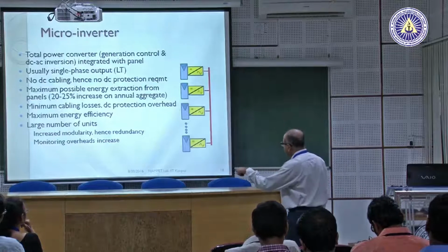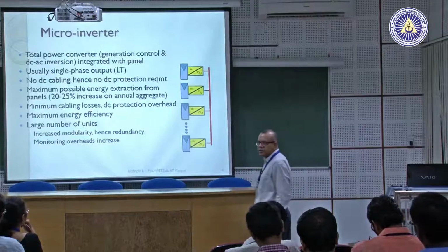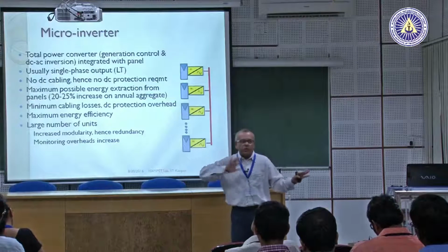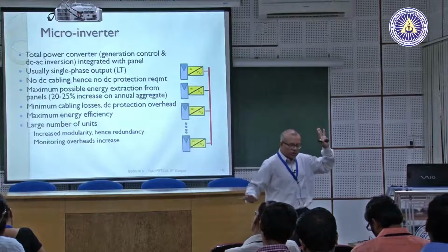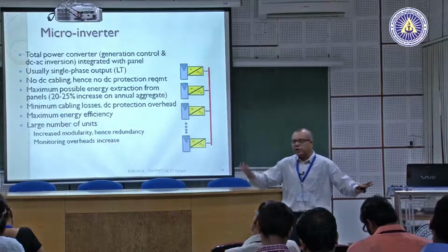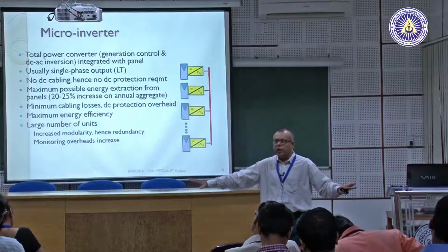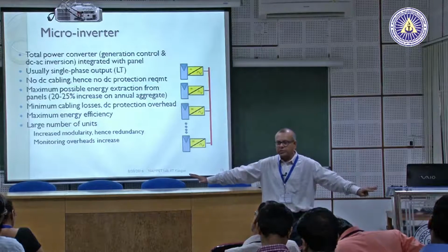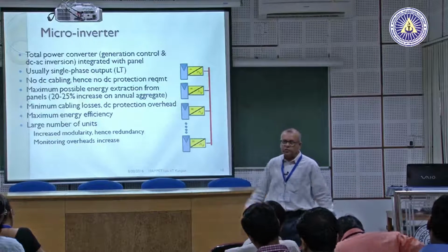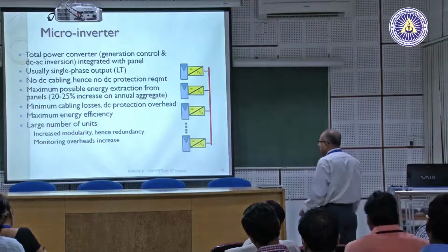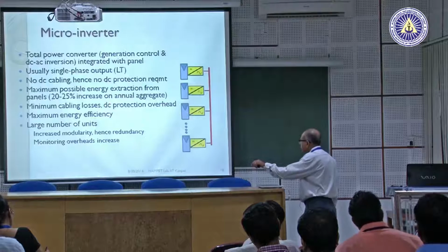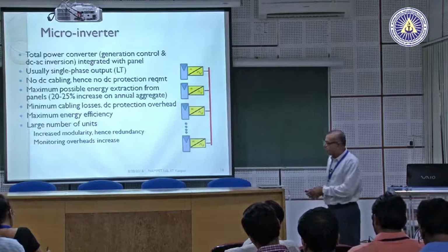Of course there are solutions—there are DC switchgears, but on an RMS current equivalent basis, let's say you have a 100 ampere AC switchgear and a 100 ampere DC switchgear, the cost is around 4 to 8 times more. The DC is obviously more expensive. That's the kind of expense we're talking about.